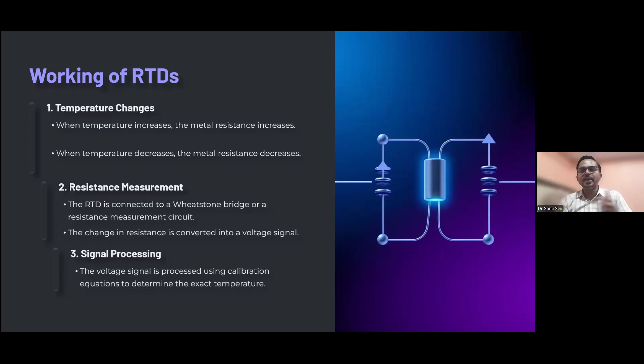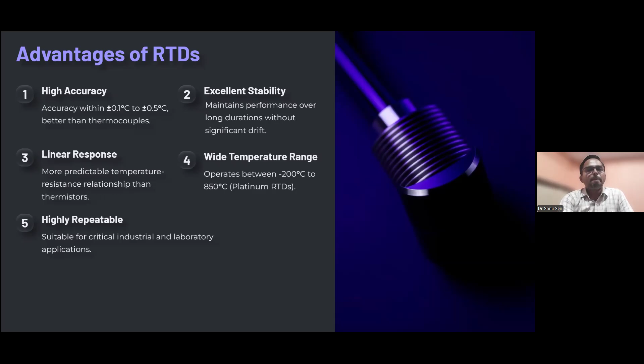Now the advantages of the RTD. High accuracy: it can measure temperature with an accuracy of plus minus 0.1 degrees to 0.5 degrees Celsius. While in the case of thermistors and thermocouples, the accuracy is in the range of plus minus 1 to 2 degrees Celsius. Then it is excellent for stability. Unlike some sensors that degrade over time, RTDs provide reliable performance for years. Linear response is there: as the temperature rises, resistance rises. So the temperature-resistance relationship is predictable and easy to calibrate. It has a wide temperature range and is highly repeatable, so it can be used repeatedly.